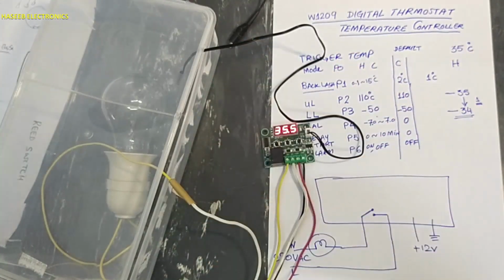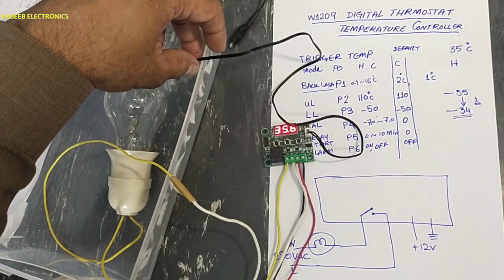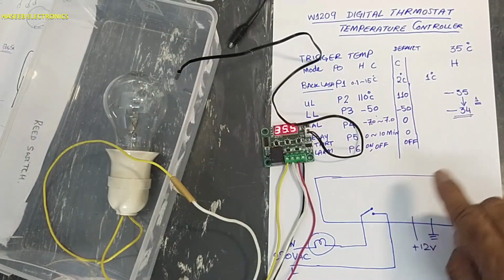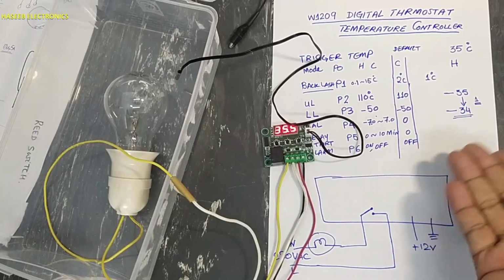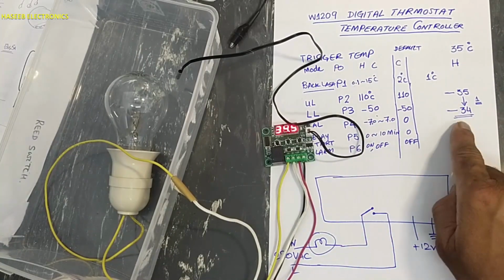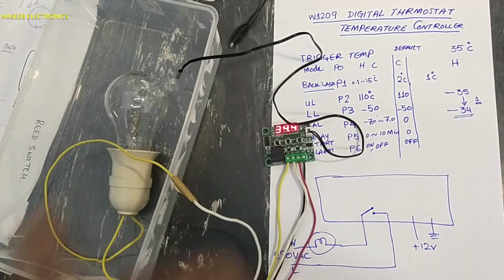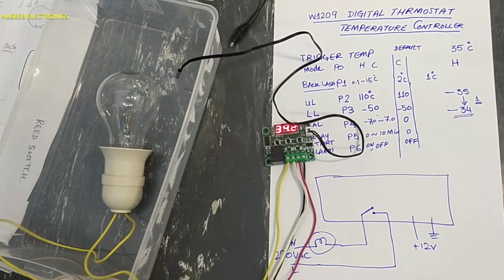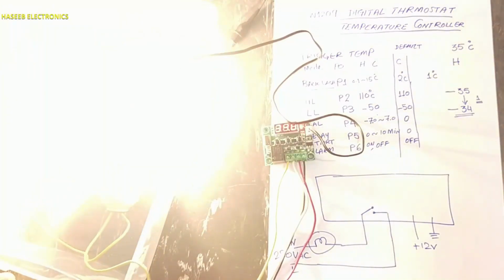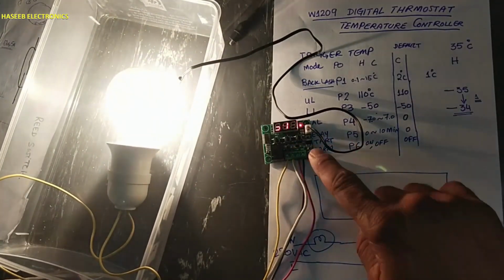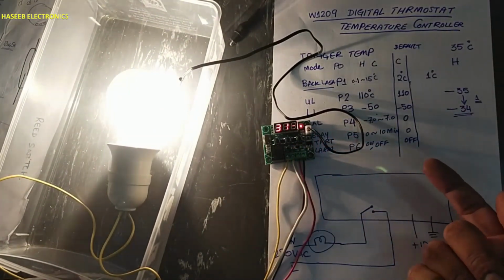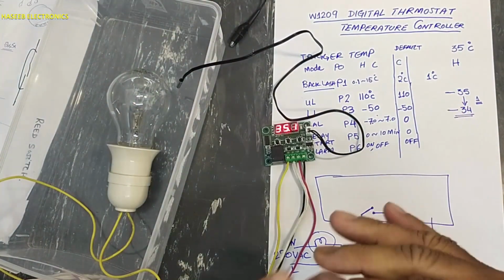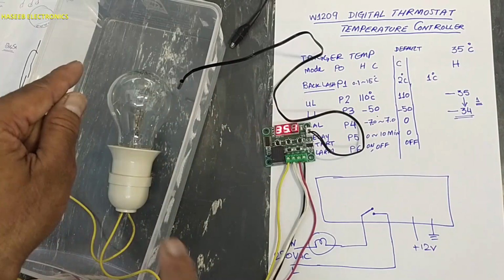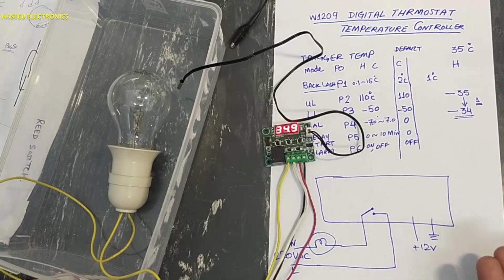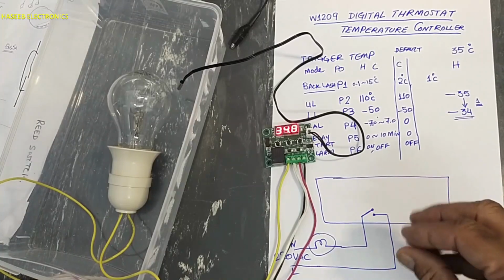Now when this enclosure temperature will decrease, when this sensor surrounding temperature will decrease until 34 degree, it will turn on again. When the temperature will decrease back to 34 degrees centigrade, it will turn on the heater again. Yes, it is now on. Now the temperature will increase again. 34.6, 34.8, 34.9, 35. At 35 it disconnected. So it will control the heat in this box. In upcoming session we will program this module for cooling mode.